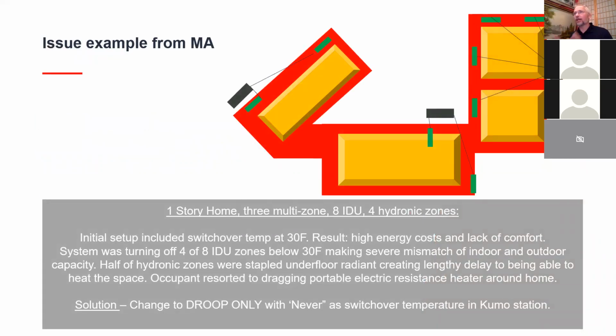And here is one of the examples that I like to refer to, just to give you an idea of what can go wrong in different scenarios. It's one of the reasons why I'm a big proponent of using a droop-only strategy and not encouraging the use of any cutover temperature whatsoever. If you're using the Kumo Station, for instance, where you have the capability to set a cutover or switchover temperature, I recommend changing it to never and just allowing the heat pump to continue to operate through the season and bring on additional heat thereafter.